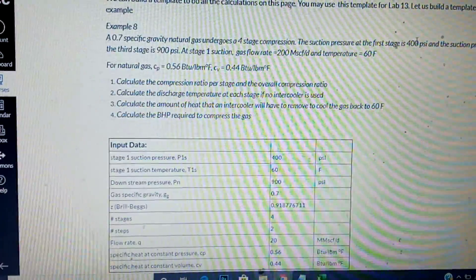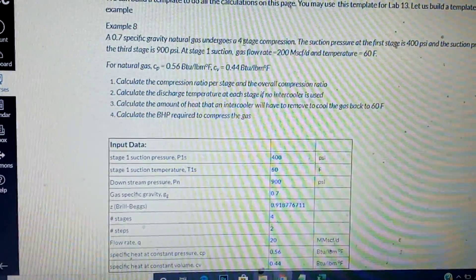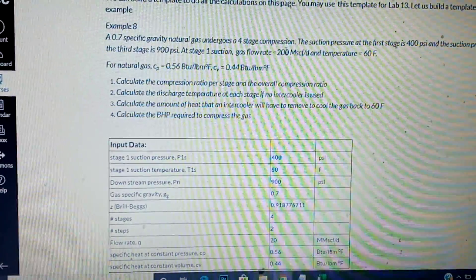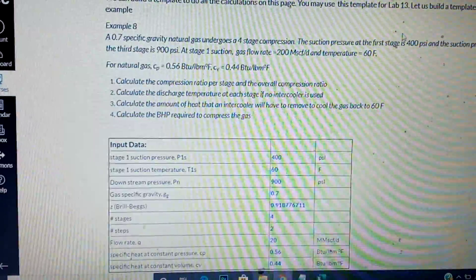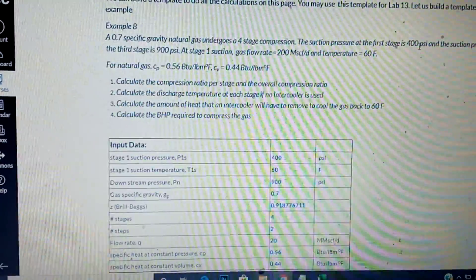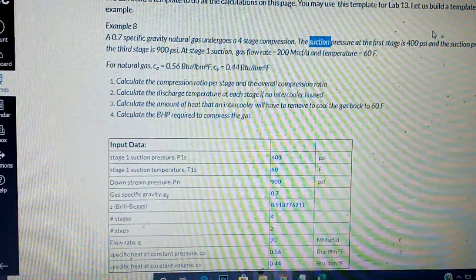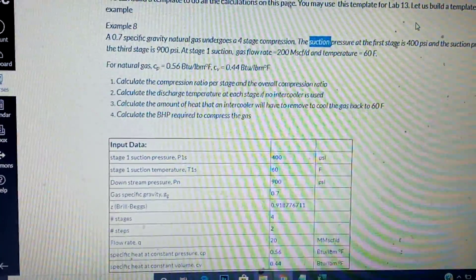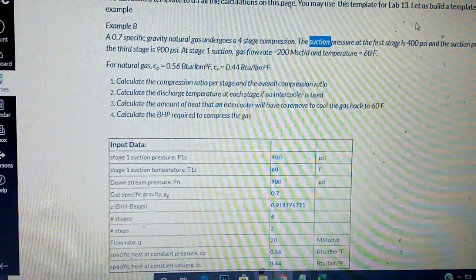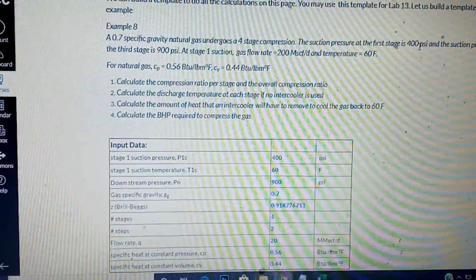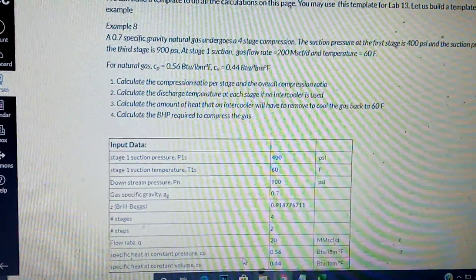If you are given the suction pressure at both stages, the number of steps will be three minus one — which is two. For the number of steps to be three, it has to go from suction to delivery. If it's from suction to suction, the number of steps is the number of compressors minus one. Since we are given suction at stage one as 400 and suction at stage three, the number of steps is two.